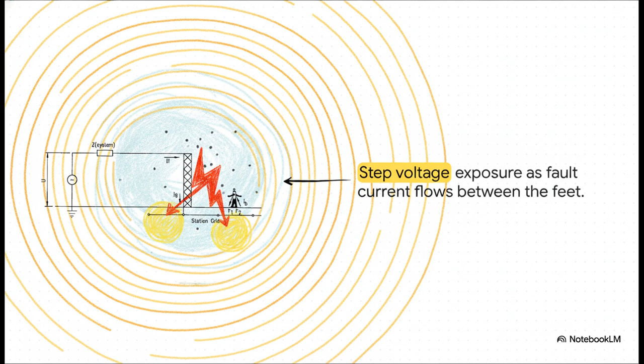Section 5. Touch and step voltages. You don't even have to be touching a piece of equipment to be in danger. If a fault happens and you're just walking nearby, the massive current flowing into the earth creates a voltage gradient right there in the soil. Because your feet are apart, they're actually sitting at two different voltage potentials. And since electricity always seeks a path to balance, a body current can travel up one leg and down the other, driven completely by the voltage difference in the dirt itself.